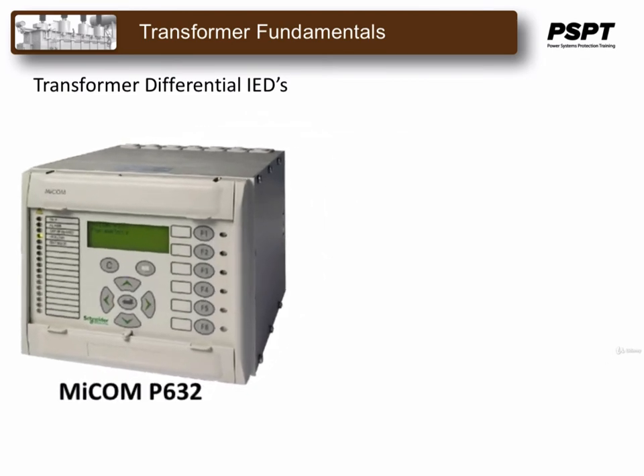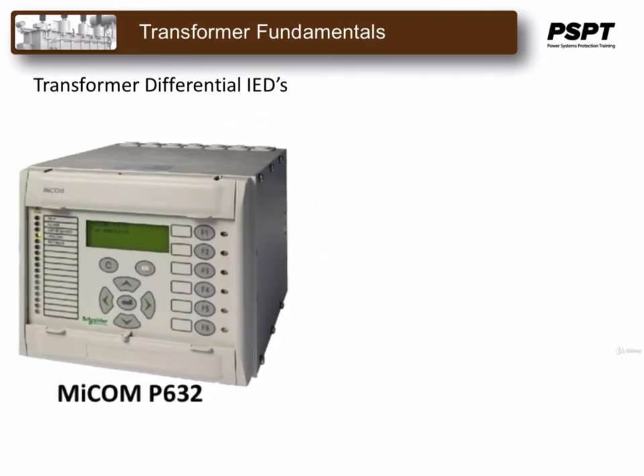The MiCOM relay is the last one, which we'll look at very quickly. The P63 series provides high-speed tripping 3-system differential protections using a triple slope characteristic and 2 high-set differential elements in combination with transformer inrush restraint, overfluxing restraint, and through stabilization.